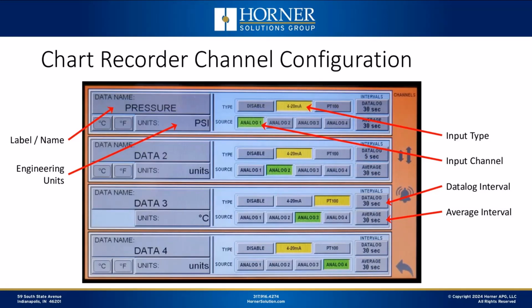So you can select the type of signal coming in, and then you can also remap which analog input is being displayed as channel 1, 2, 3, or 4. You can have the same analog input mapped to 2 different channels that are maybe scaled slightly differently. You could do that if you wanted to. So you've got a lot of flexibility there.